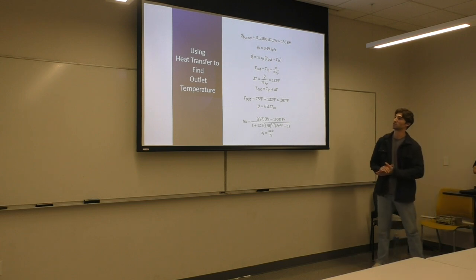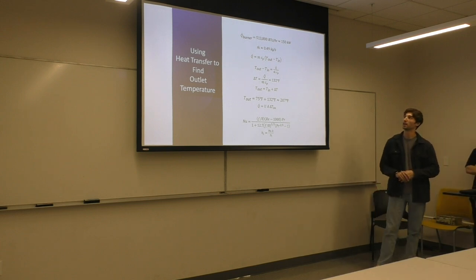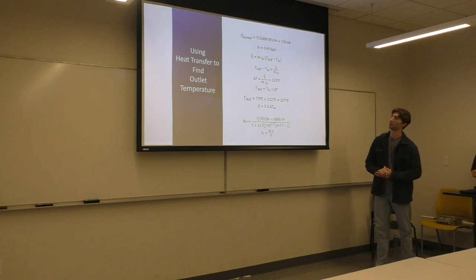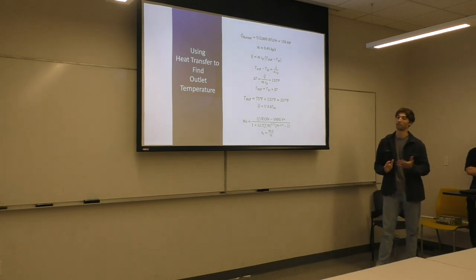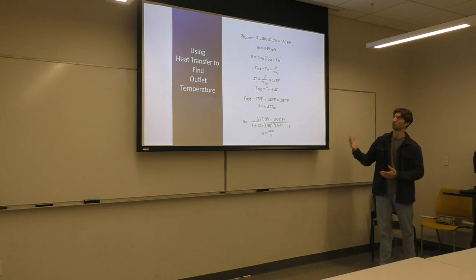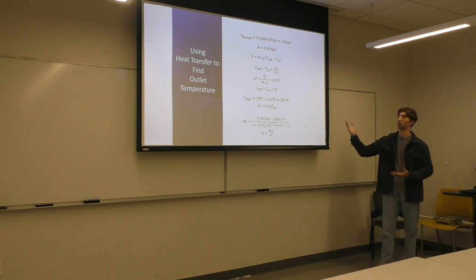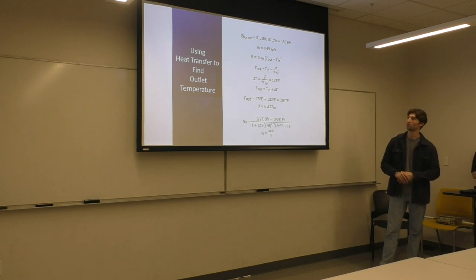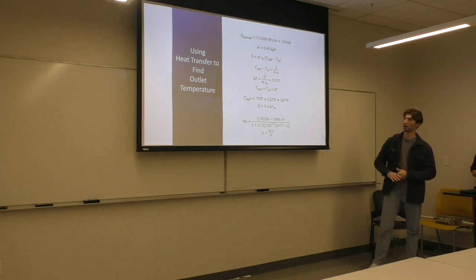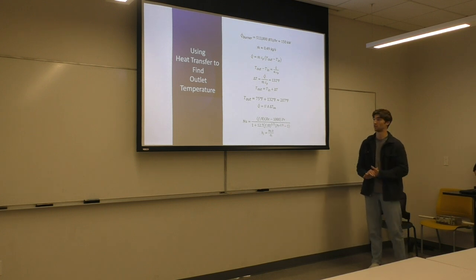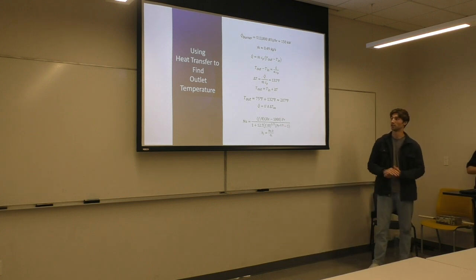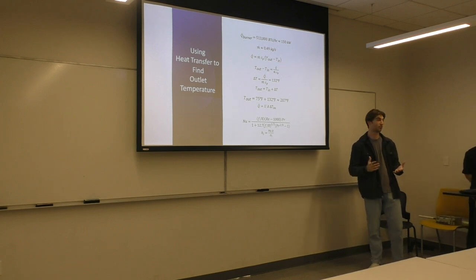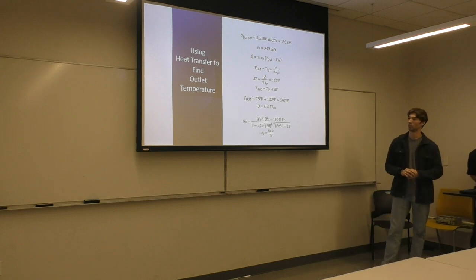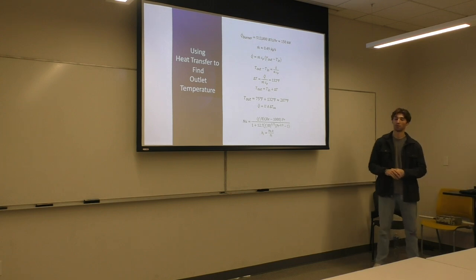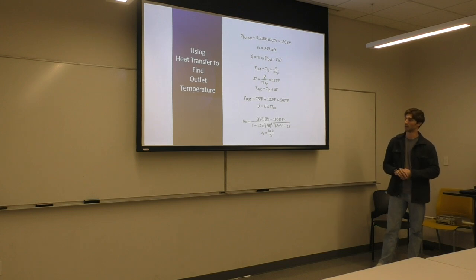Okay, so here are some calculations we could use. We could do the energy balance at the top, where our burner produces 150 kilowatts of power. The mass flow rate from the 8 gallons per minute is about 0.49 kilograms a second. Finding our delta T to be 132 degrees Fahrenheit, and with an inlet temperature of 75 degrees, we can say that the outlet temperature would get to 207 degrees Fahrenheit. This doesn't account for some losses and a lot of other factors. If I put in 32 degrees Fahrenheit water, it's still going to get close to 200 degrees, so it's not completely accurate.